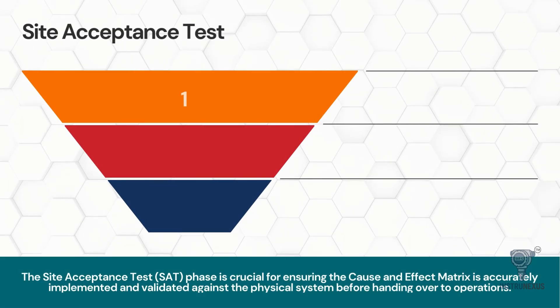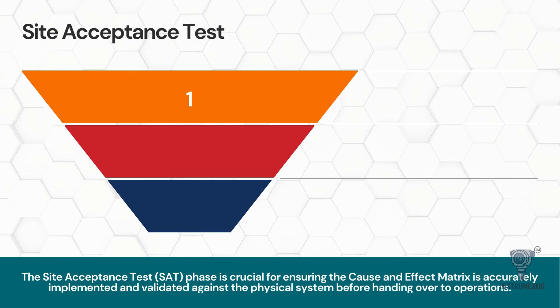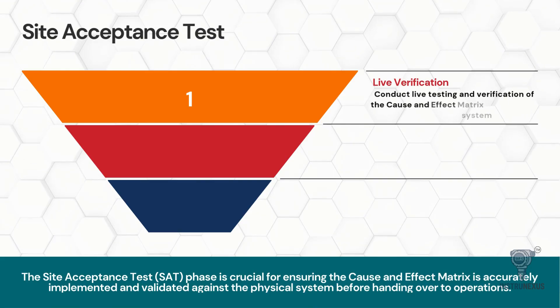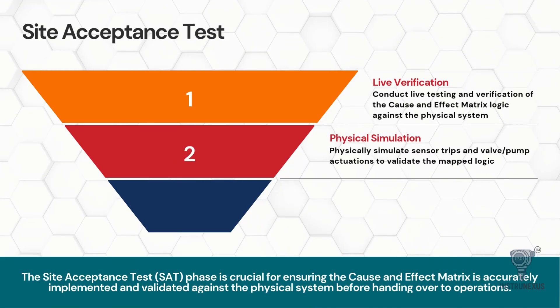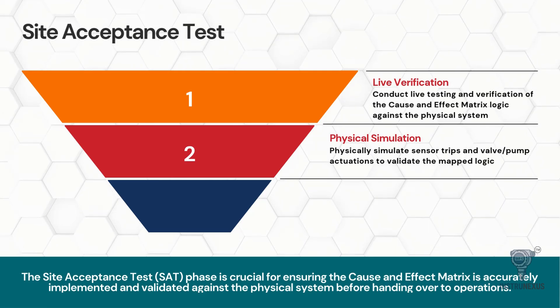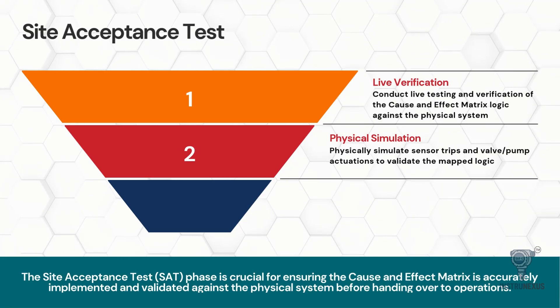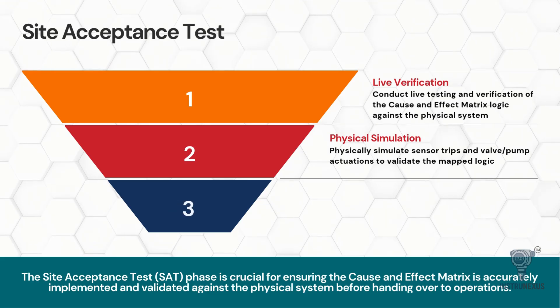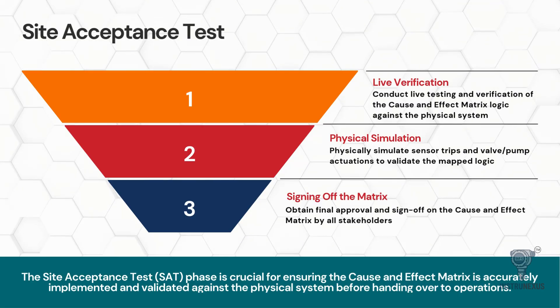With construction complete and the code loaded, we reach the site acceptance test, or SAT. This is the moment of truth. Unlike the FAT, which was virtual, this is live verification. We conduct physical simulations on the actual hardware. We might inject a signal into a pressure transmitter to fool it into thinking pressure is high and then physically watch the shutdown valve close in the field. We are validating the mapped logic against the physical system's response. Once all tests pass, we obtain the final sign-off on the cause and effect matrix from all stakeholders, certifying the plant is safe to start.